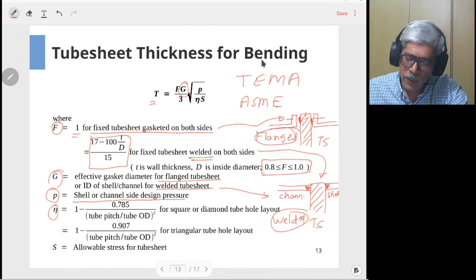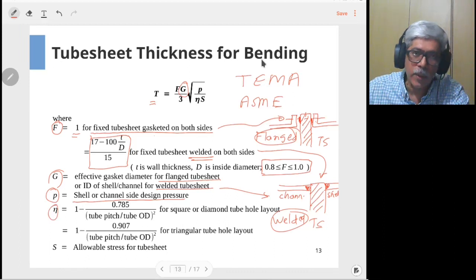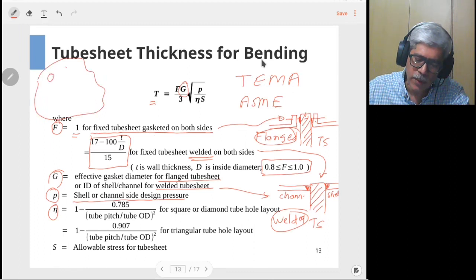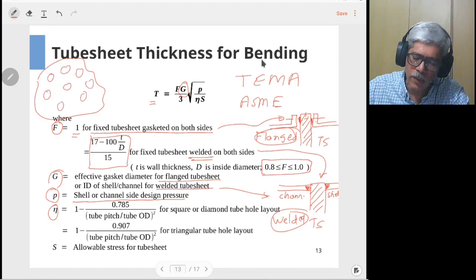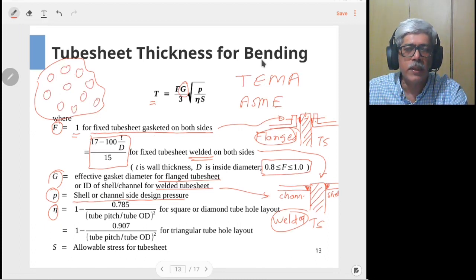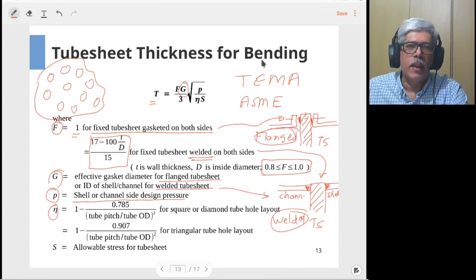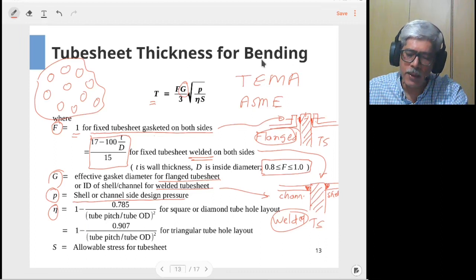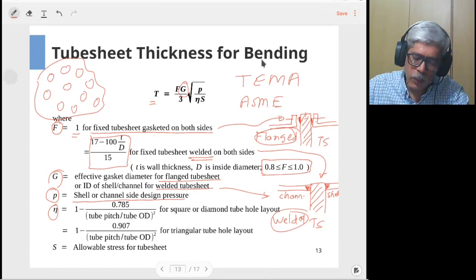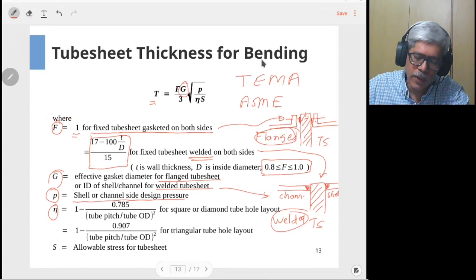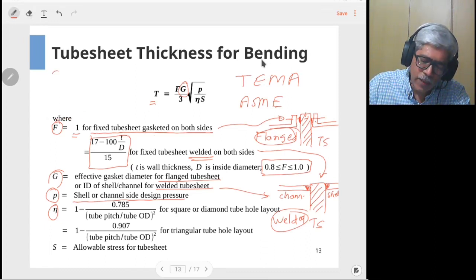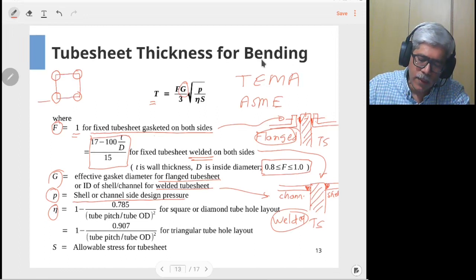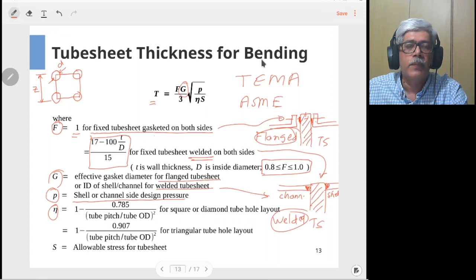P is the shell side or channel side design pressure, whichever is higher. The parameter η is known as the ligament efficiency. The tube sheet is a perforated plate because holes are drilled through it to attach the tubes, which makes the tube sheet weaker than a solid plate. To account for this weakness, the ligament efficiency of the tube hole pattern is included. For a square layout, the tubes are arranged in a square pattern with pitch Z and hole diameter D.